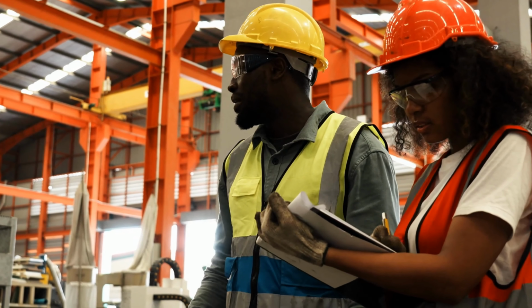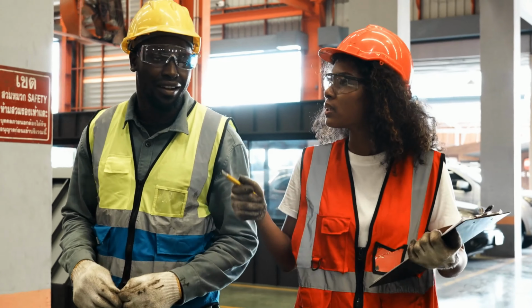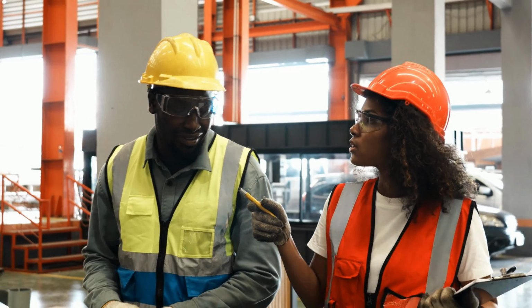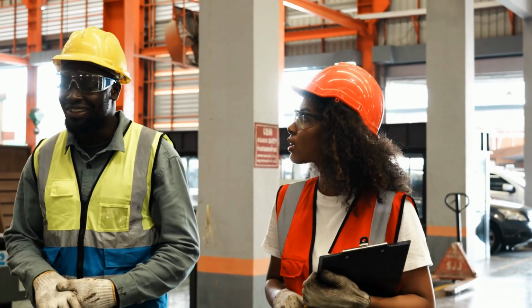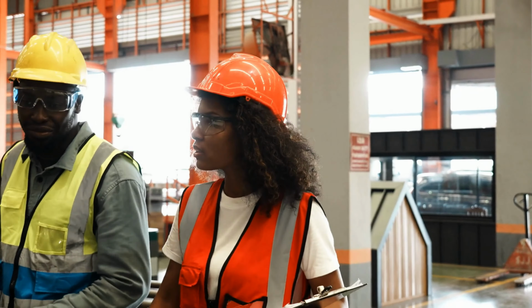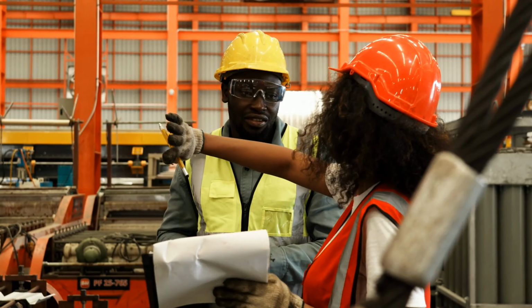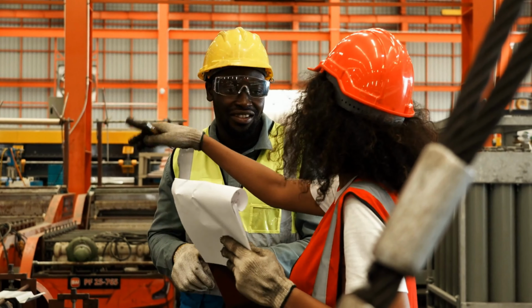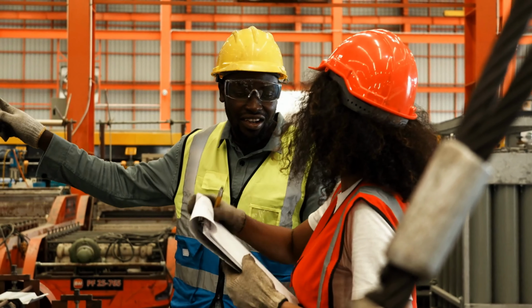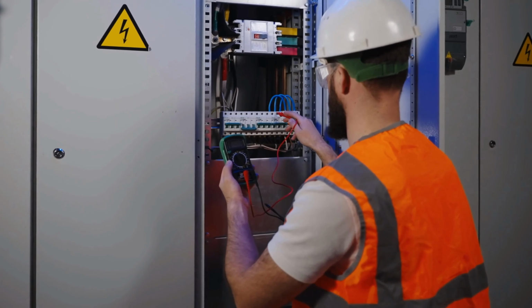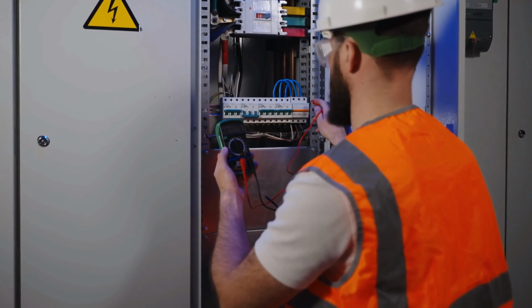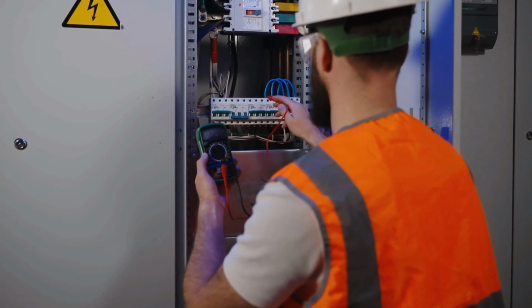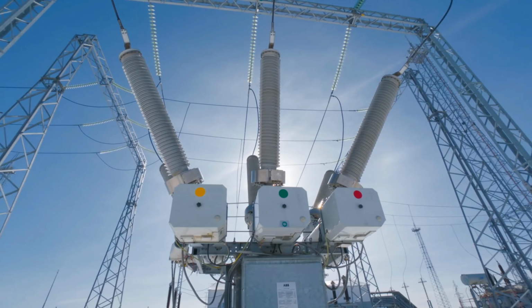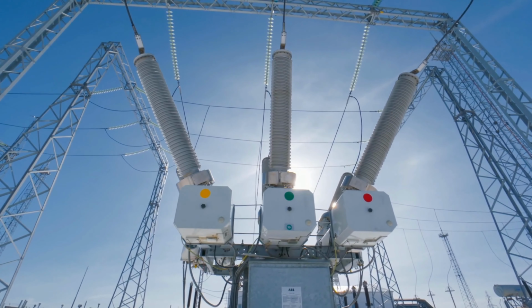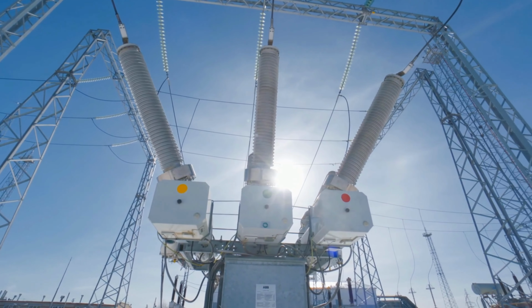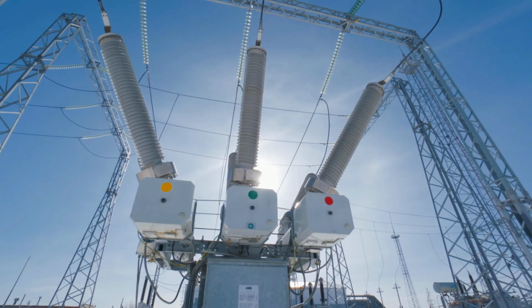4. Prevention and safety measures. Personal protective equipment, PPE: flame-resistant clothing, gloves, helmets, face shields, and ear protection. Proper training: workers should be trained on electrical safety and hazard awareness. De-energizing equipment: always turn off and lock out equipment before maintenance. Arc-resistant gear: use arc-resistant switchgear and enclosures to minimize risks. Regular maintenance: inspect and maintain electrical systems to prevent faults. Safety labels and barriers: clearly mark hazardous areas and restrict access to unauthorized personnel.